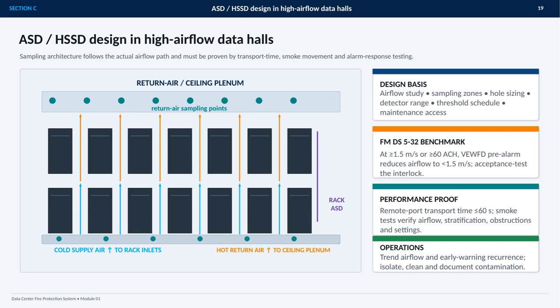The central principle is that sampling architecture must follow the actual movement of air, from cold supply air at the rack inlets, through the racks, and into the hot return air path and ceiling plenum. The design has to be proven, not simply drawn. That proof includes airflow studies, defined sampling zones, hole sizing, detector range, alarm thresholds, and practical maintenance access.